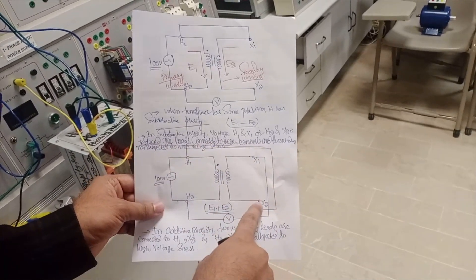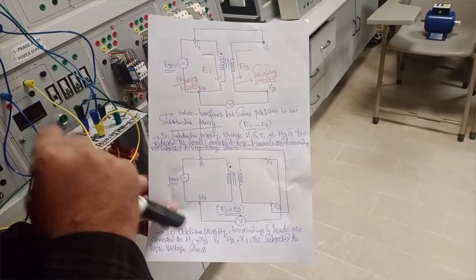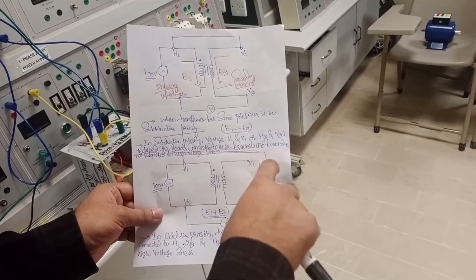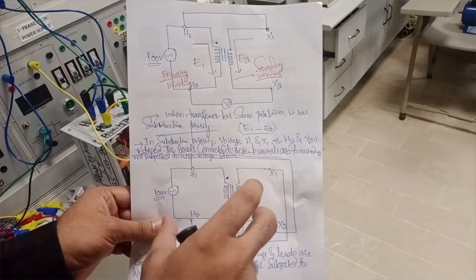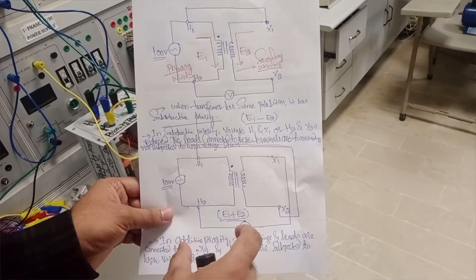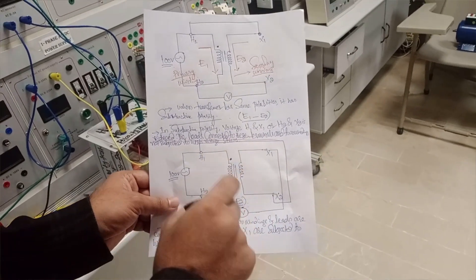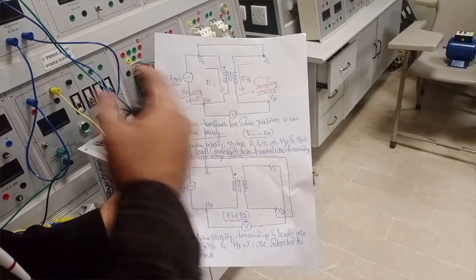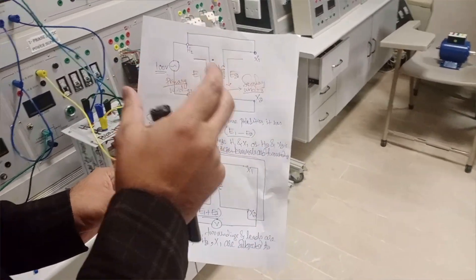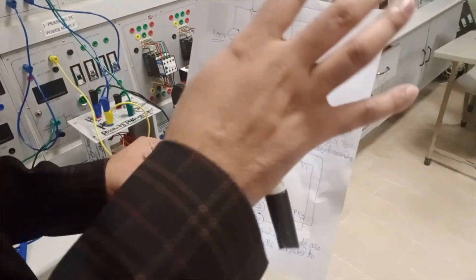In the additive polarity diagram, H1 is connected with X2 and H2 is connected with X1, while H1 and H2 are again connected with the supply side. This gives us voltages that are additive in nature, and the windings and terminals of the transformer will be subjected to high voltage stress — whereas the subtractive connection results in low voltage stress. We practically prefer the subtractive polarity because the leads and windings are subjected to less voltage stress.